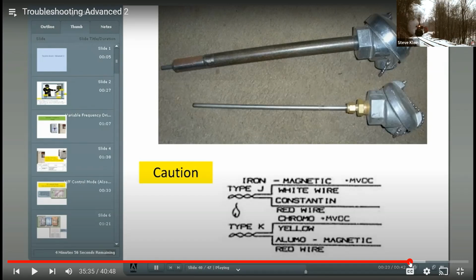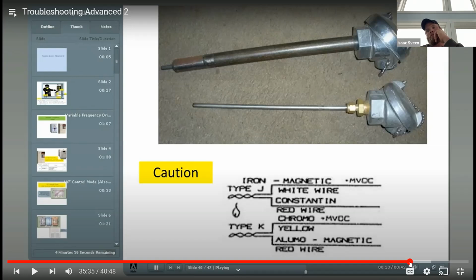If you get caught out and you do lose a probe like that, if you can at least take the wires and twist them together nice and tight, if it's like a type J thermocouple, that will give you a reading. Don't leave it in there very long. Get the probe on as quick as you can. But you might be better off just sticking the wires in than actually trying to use a big heavy probe, because the reaction time is going to be that much slower.